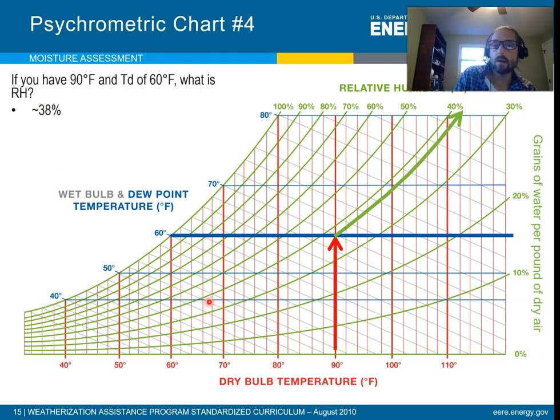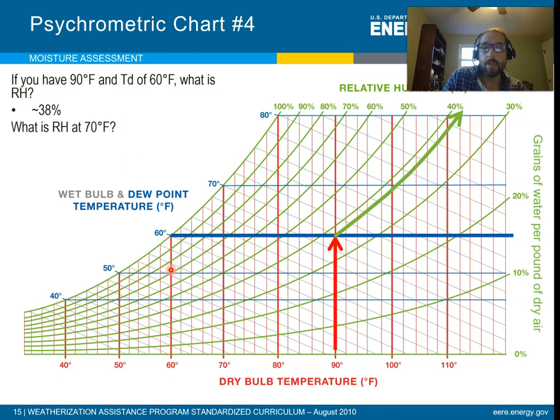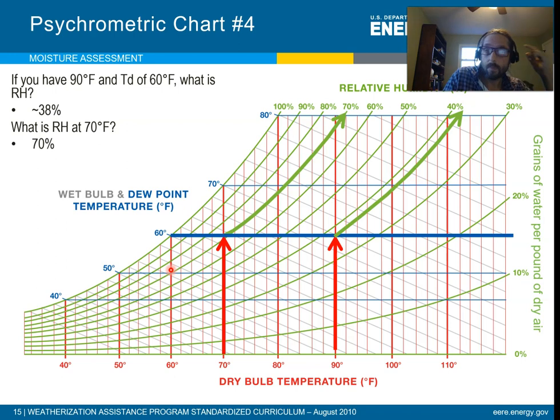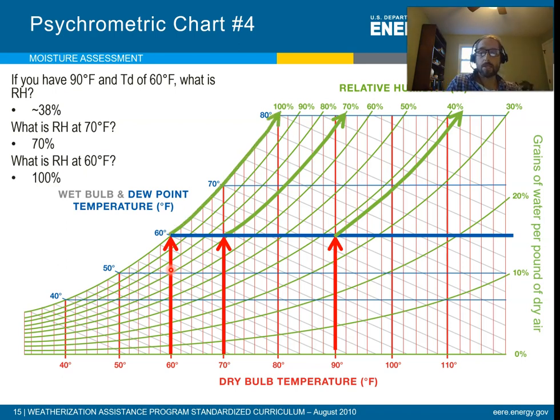Let's go the other direction. Our same starting point: 90 degree dry bulb, 60 degree dew point, 38% relative humidity, which would be about a 70 degree wet bulb. Now we cool the air down to 70 degrees — our relative humidity is now 70%. What if we go all the way to 60? You'll notice 60 degrees is our dew point, so if we get all the way to 60, we're at actually 100% relative humidity.